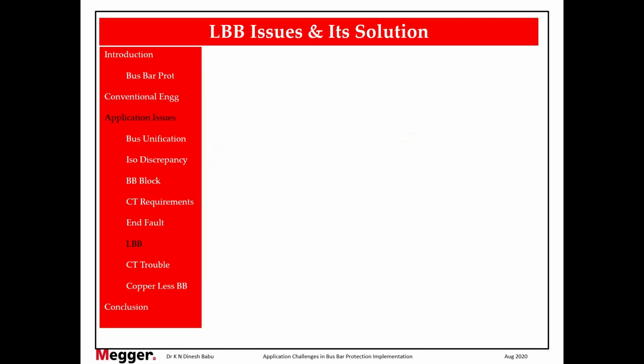Okay, next, moving on. Local breaker backup. So we all know what LBB is. Now we are going to see only one key issue. Breaker failure initiation has resulted in several unwarranted operations of bus bar. We have seen several cases where the bus bar tripped, and on what protection has it tripped? LBB has tripped. Okay, who has sent the LBB? One particular distance protection relay has sent the LBB. Let us go and analyze the distance protection relay. We find that the distance protection relay did not send any initiation signal. What is this problem? We have seen this globally. Many places, many countries have reported this issue.